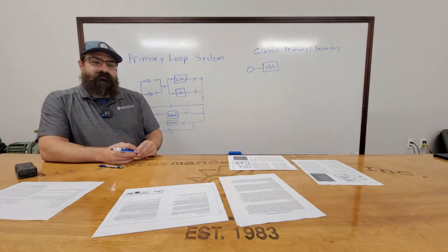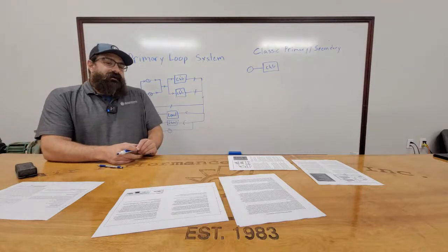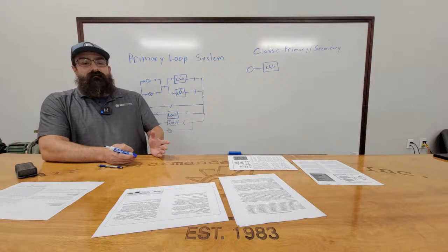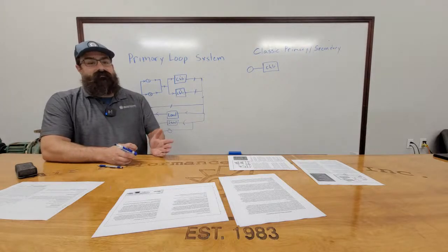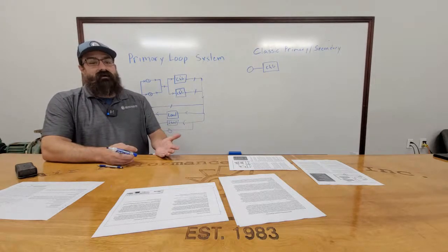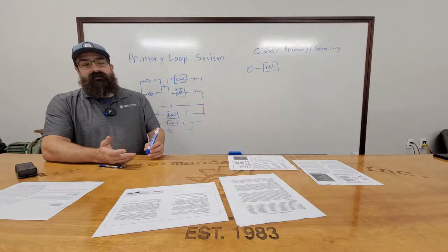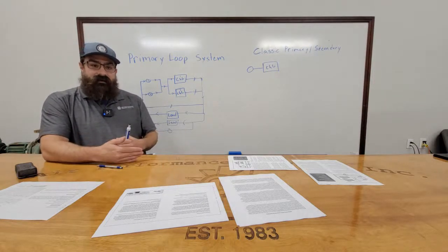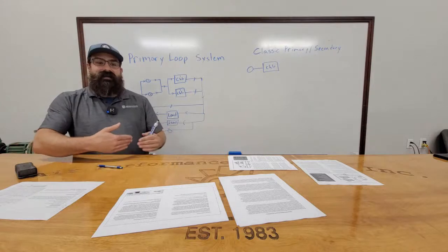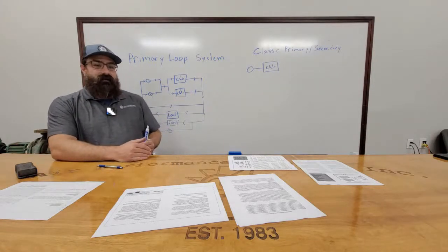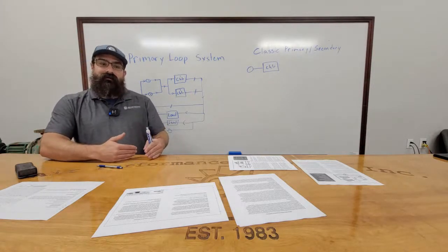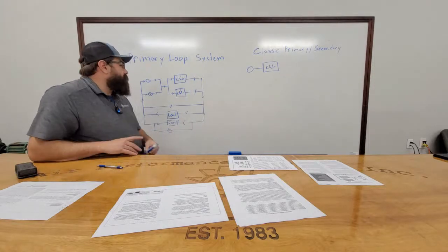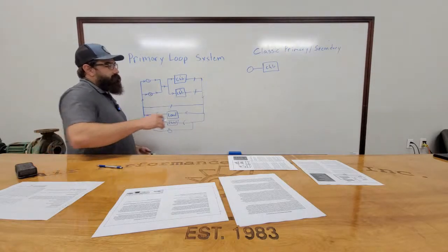And you're still running two pumps. So, I'd have to check it. I haven't checked it in a while. But yeah, and the pumps are not on VFDs either. So that's part of the issue. Constant duty. Well, it's got a bypass valve. Okay. So that's how we maintain pressure, with the bypass valve. But we have to run both pumps and then modulate the bypass valve. In theory, we should be able to run one pump and modulate the bypass valve, but we can't. It just doesn't work.